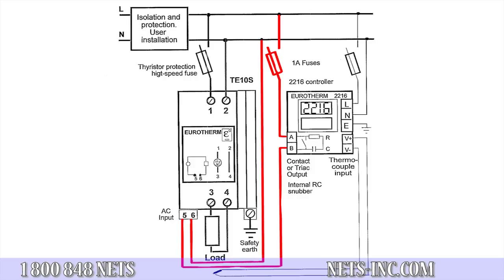To complete this AC circuit, wire terminal 6 from the power controller back to neutral. Now when the temperature controller turns on or off the relay or triac, it will pass the line voltage signal to the input command of the power controller, and the power controller will turn on to allow current flow to the heating element.